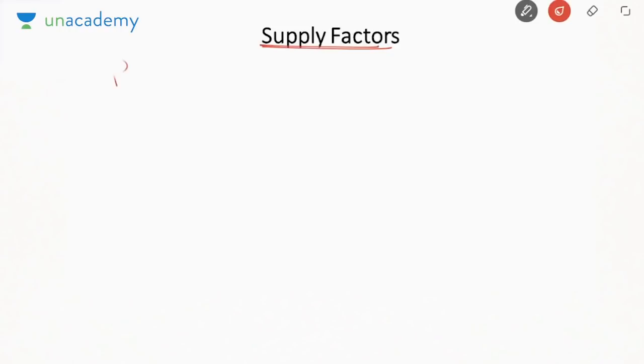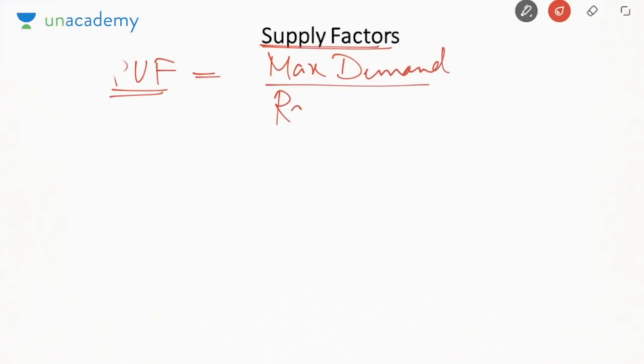First is the plant utilization factor. It means how efficiently you are utilizing the plant. It is maximum demand by rated capacity. Suppose maximum demand is 150 megawatt, then your capacity should always be higher as you must be able to meet the demand. So this factor is less than 1, but it must be as close to 1 as possible so that we are effectively utilizing the capacity.